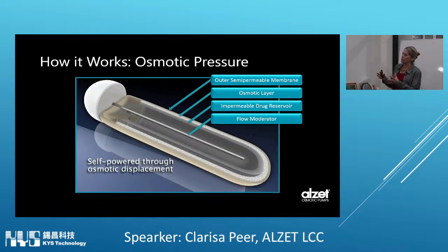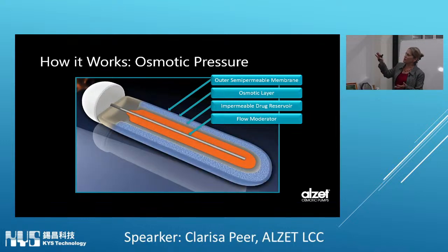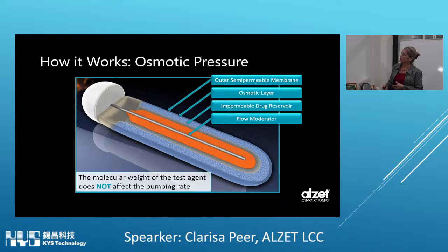This is a flexible reservoir where the drug sits after you inject it into the pump. And this piece called the flow moderator, which is a stainless steel tube with plastic at one end. This is where the drug goes out as it's being delivered. So when you implant the pump into the animal, interstitial fluid comes into the pump across the outer membrane, causes the salt layer to hydrate and to swell, and squeezes the drug reservoir and pushes the drug out through the hole at the end of the pump. For this reason, we know that the molecular weight of the test agent that you put inside does not affect the pumping rate.